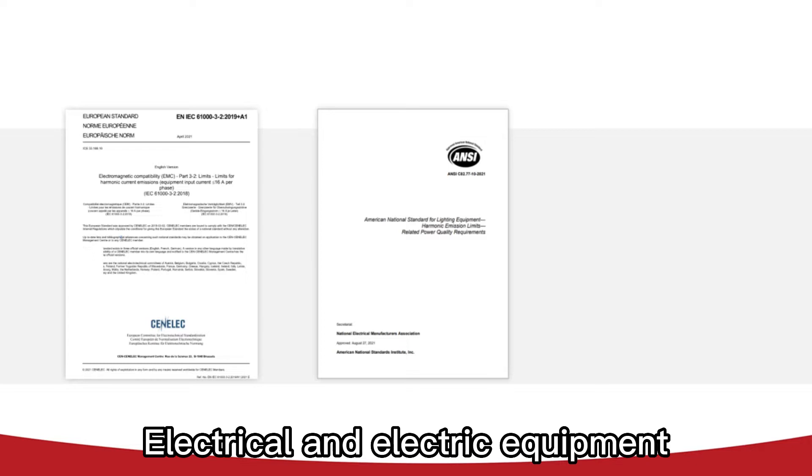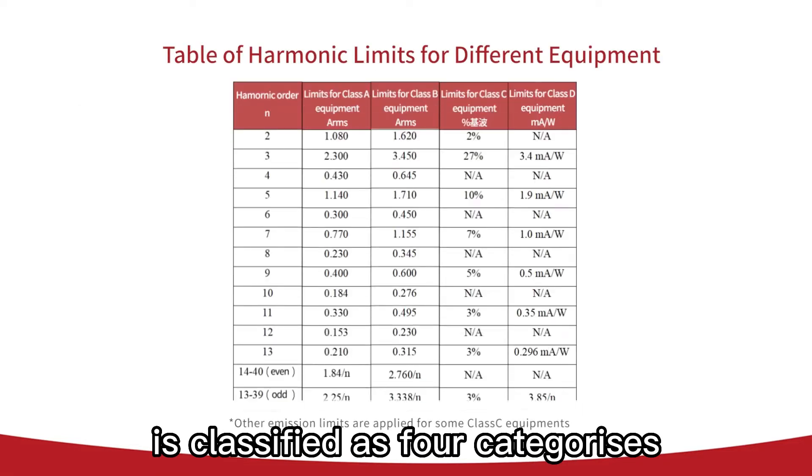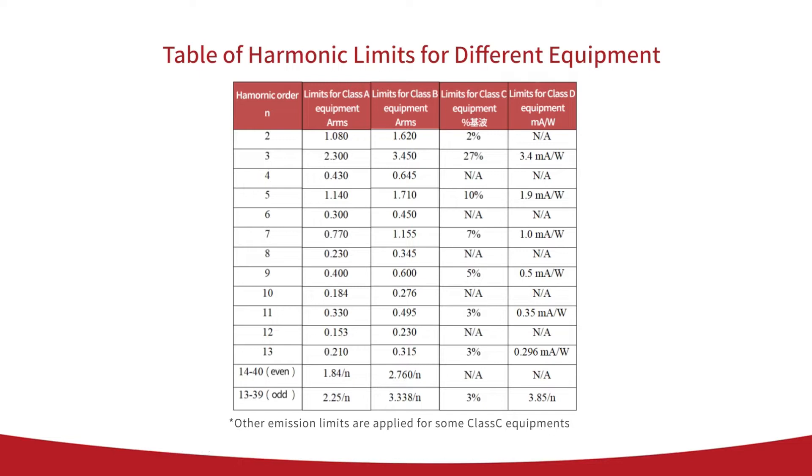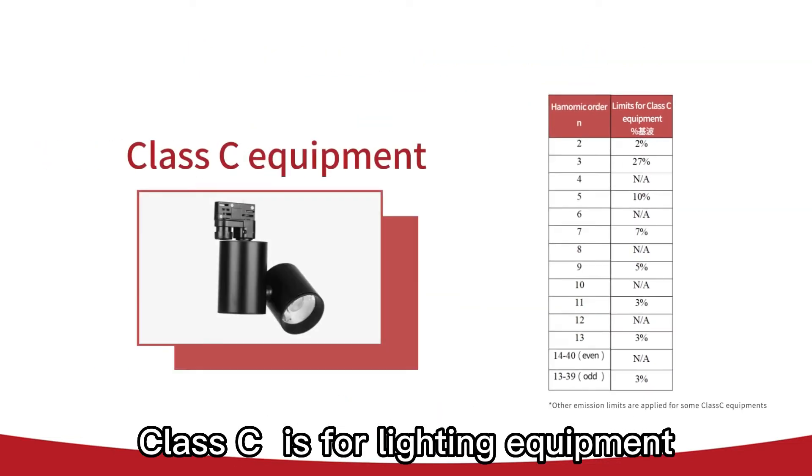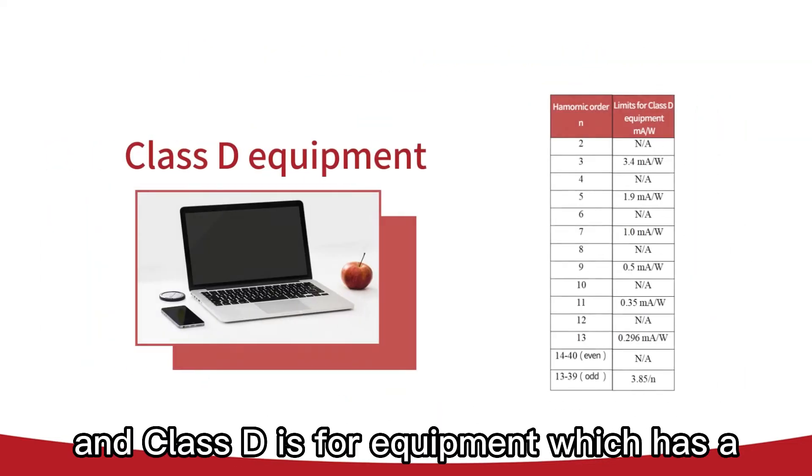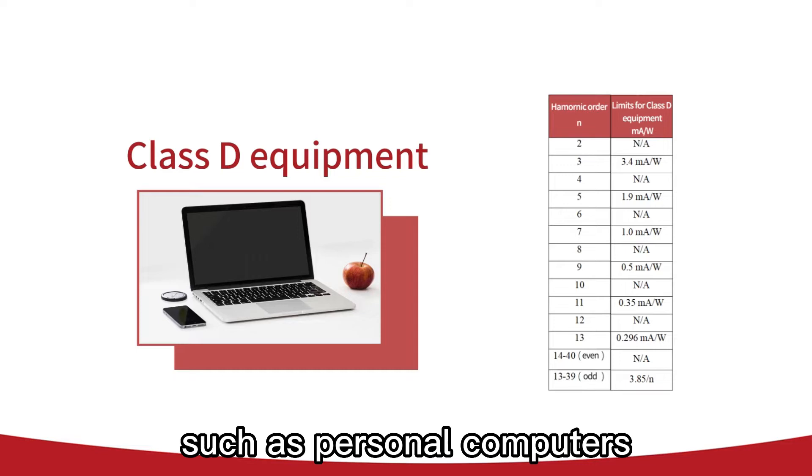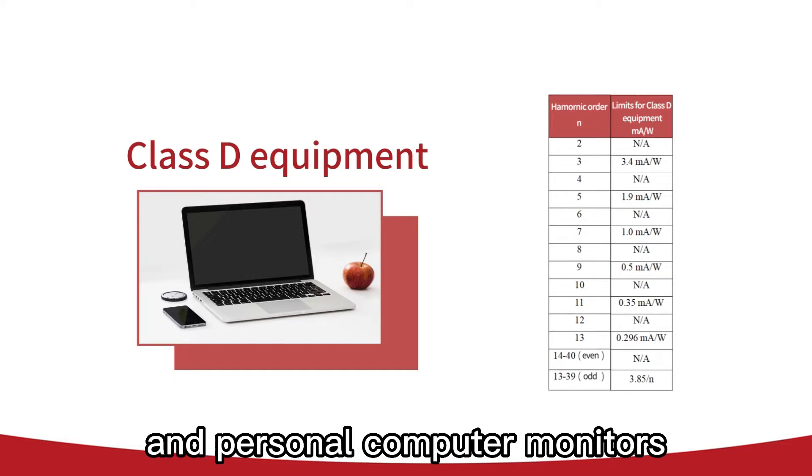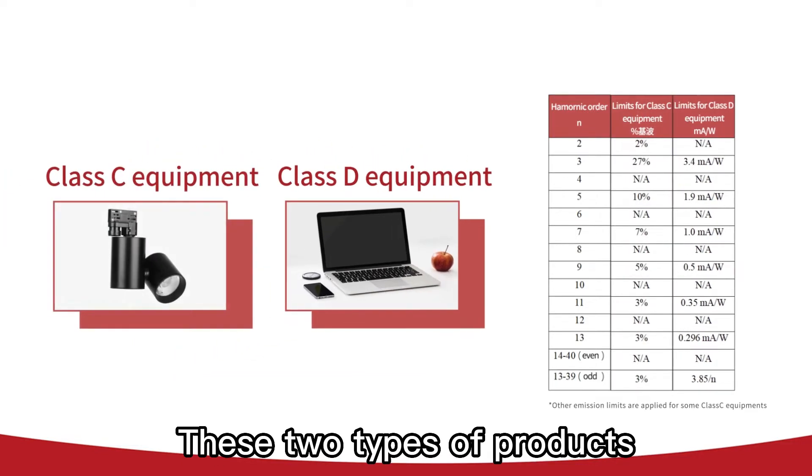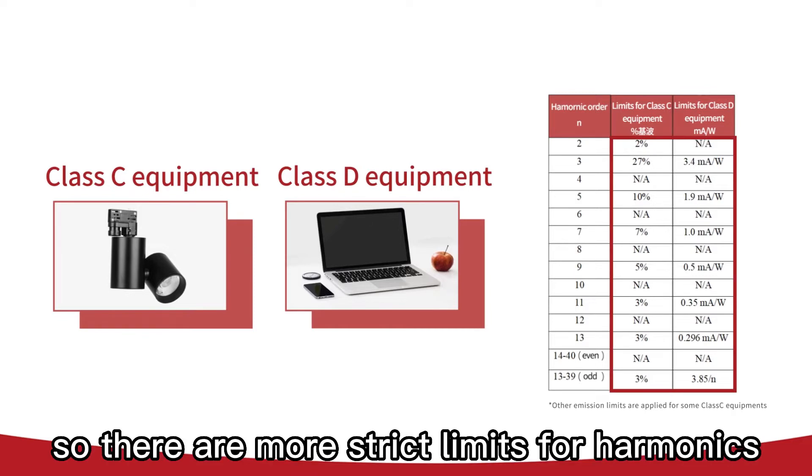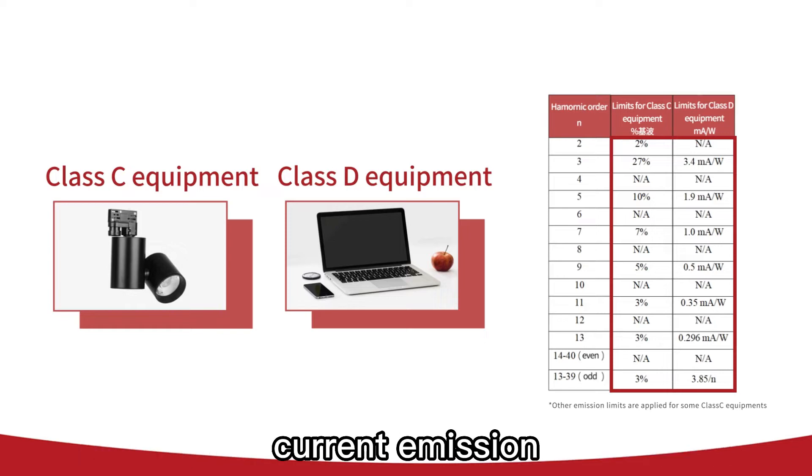Electrical and electronic equipment is classified as four categories according to the latest IEC standard. Class C is for lighting equipment and Class D is for equipment with specified power less than or equal to 600 watts such as personal computers and personal computer monitors. These two types of products are numerous and frequently used daily, so there are more strict limits for harmonic current emission.